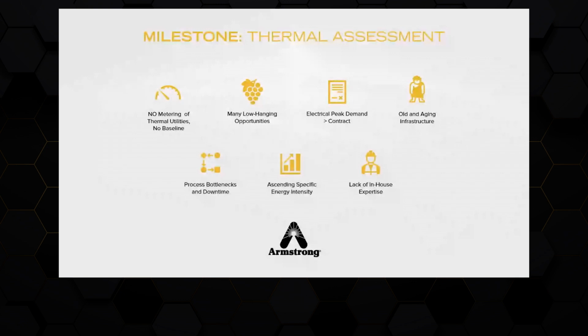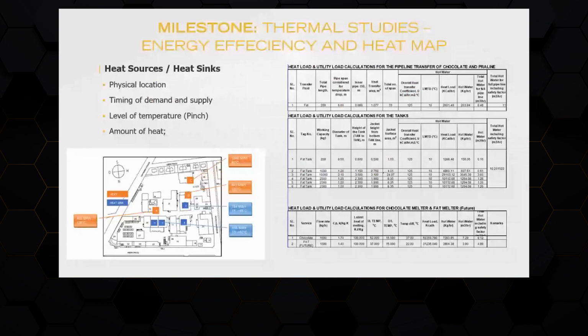Post-thermal assessment, we started with a measurement campaign with ultrasonic flow meters and data loggers to measure flow and temperatures of all the utilities. Though there was a lot left to be desired on utility metering, the chocolate plant had excellent metering when it came to raw material and process flows and of products. So we were able to collect quality process flow data from plant instrumentation. The collected data helped us to create a heat map of the facility.